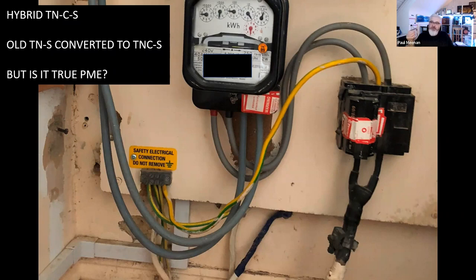So when they do those joints, they should theoretically, under the DNO standards, and Gordon will correct me, lay a rod next to that joint as a low impedance earth. And as Mr. Ward has talked about previously, in theory, PME and TNCS is a very safe system because multiple earthing means that your rising potential in the ground is sufficiently low and the impedance is low enough to protect persons in the network. Am I wrong or correct, Gordon?